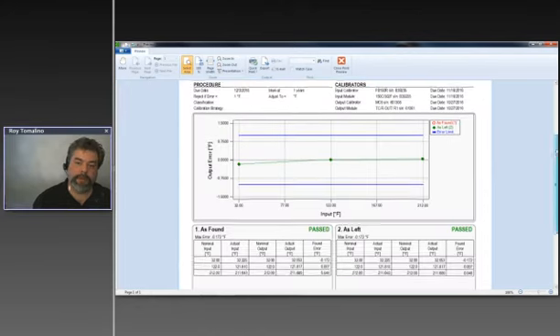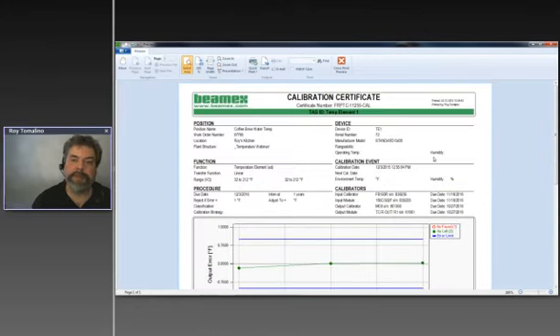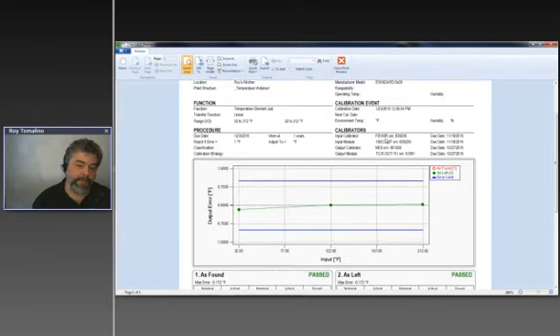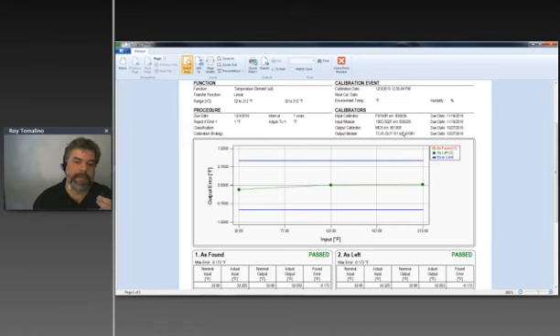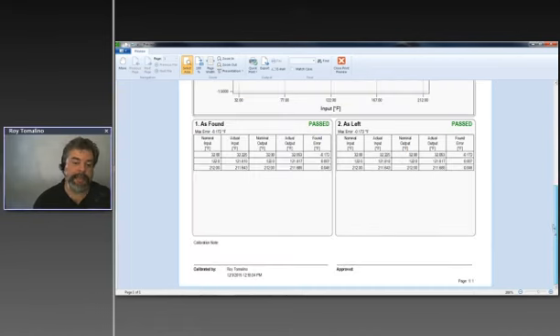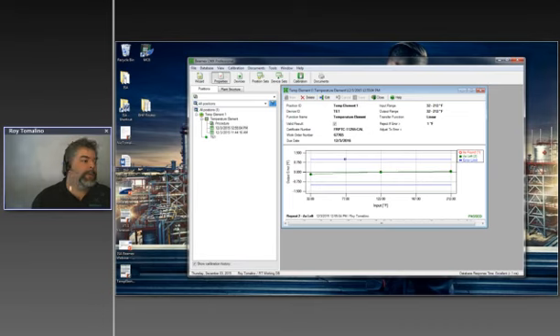So here we go. This is our calibration certificate, and we calibrated the temperature element only. We didn't do a temperature loop, even though we could have. Here's the calibrator. The dry block itself was our calibration standard, so that's listed in the input as our standard. The calibrator is the standard for the output. Here's our graph, the raw data, followed by who did the calibration. So let me close that.